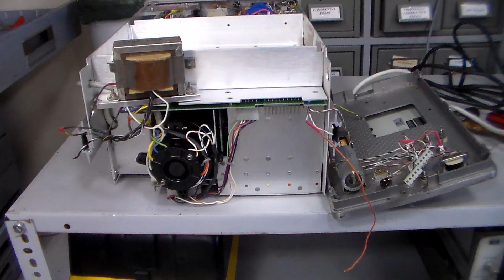Anyway, in taking the back panel off, I found that some of the wires were a bit short and had come off of the output level adjustment for the tracking generator. I'm also pretty sure that panel has been off one or more times before, because these wires just broke fairly easily. Now, this type of wire wasn't designed to be super flexible and fatigues fairly quickly when bent, but some of these were only holding on by one or two strands - the strands had been broken in the past.